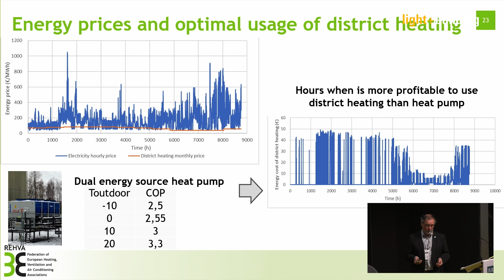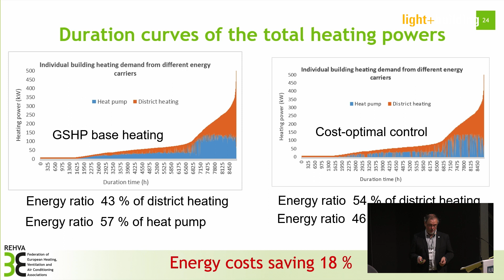When we look at this similar duration curve, if we use ground source heat pump as the base heating and district heating on top of it, the energy ratio is around 57% for the heat pump and 43% for district heating. When we change to the cost optimal method, utilizing the dynamic price of electricity and district heating, we consume more district heating than heat pump. And again, we have varied COP for that. This analysis is done on an hourly basis, and based on that we are able to reach around 18% energy saving with this control strategy.